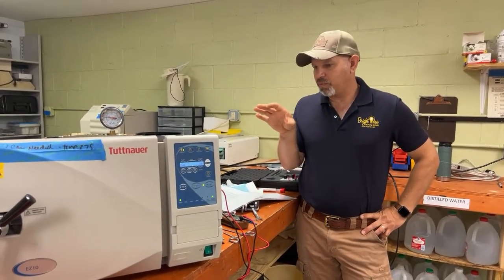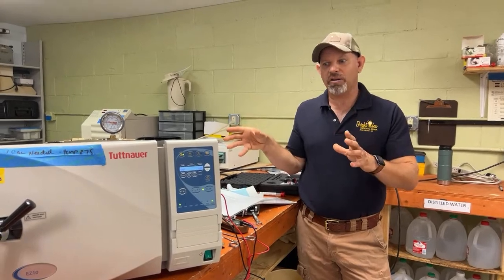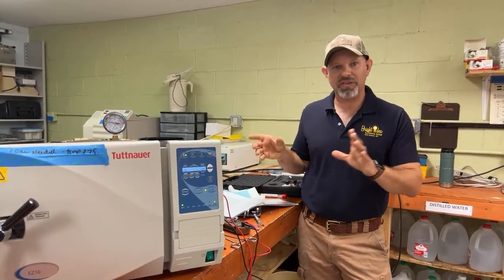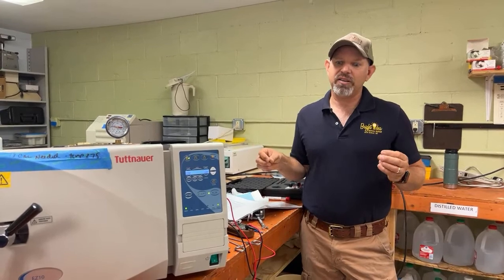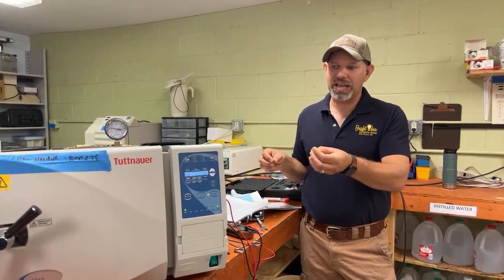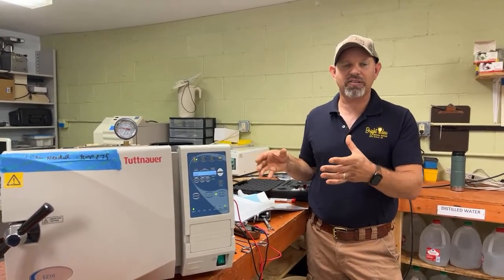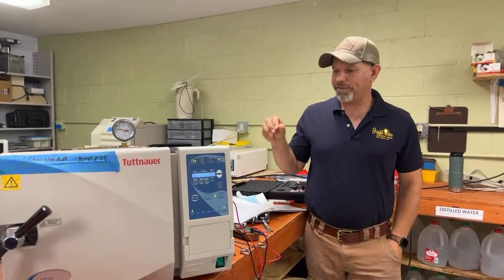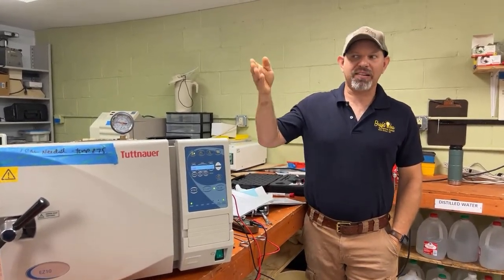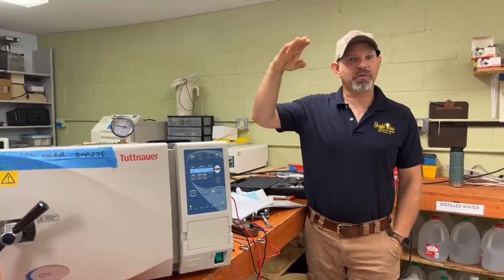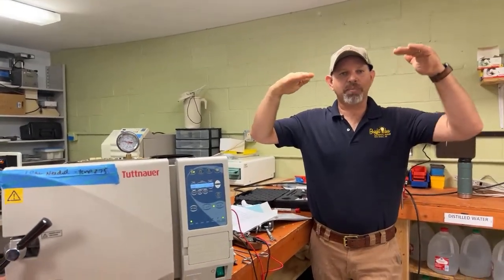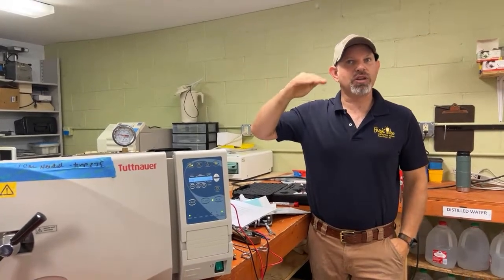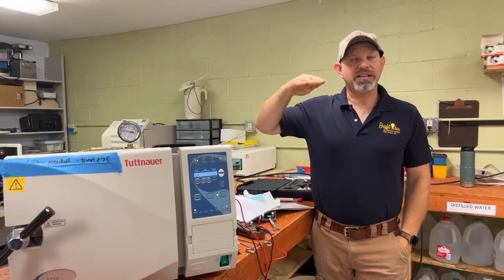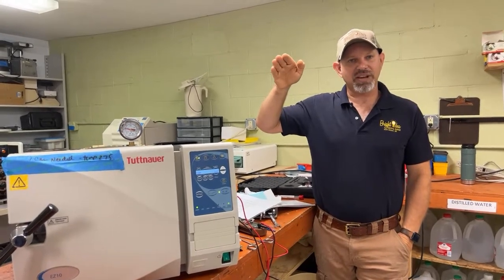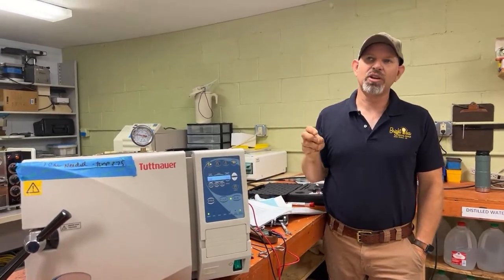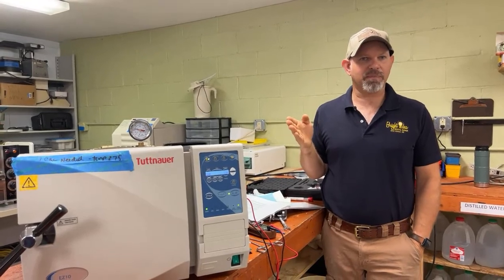So the calibration of this, we did the main part of following the book and doing it. Now the second part of the calibration is paying attention to the unit and making sure that it's functioning. What I found is that one possible thing to look out for is that when we get to that upper range, the pressure or the temperature might be a little bit too low, so that it doesn't activate the sterilization cycle, because I believe the sterilization cycle starts at between 28 and 30 pounds of pressure.